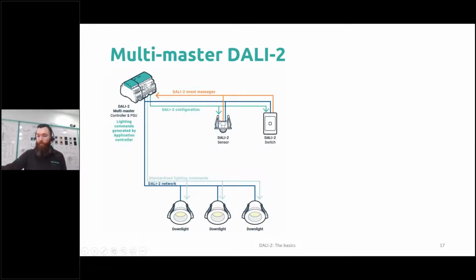So we've moved all of that intelligence back to the application controller on the line. A lot of the time this is going to be a DIN rail, that's a very standard way of installing an application controller, but it's not exclusive. You could have an application controller built into a light, a switch, or a sensor, or you could have an application controller and a little module that just sits behind your wall box. But for the purpose of what we're doing here, a DALI 2 system needs an application controller somewhere, and it will listen to those event messages.